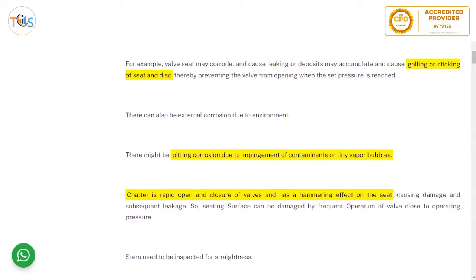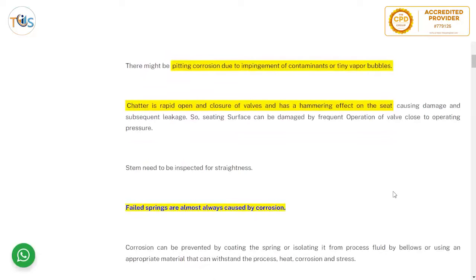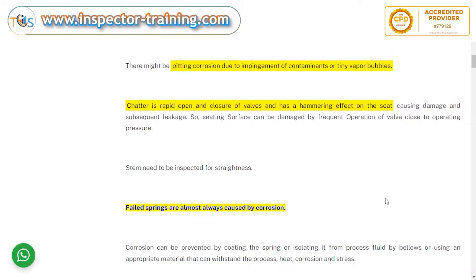There can also be external corrosion due to environment, and pitting corrosion due to impingement of contaminants or tiny vapor bubbles. Chatter is the rapid opening and closing of valves, which has a hammering effect on the seat causing damage and subsequent leakage. Seating surface damage can occur when the valve set pressure is too close to the operating pressure.